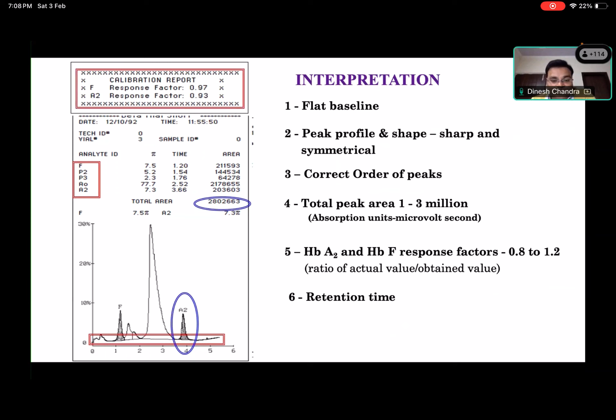Before interpreting any graph, we should always look at it very carefully for a few things. Whether the baselines are flat, then what is the retention time of your A2, then all the peaks. It should not be that A2 comes before A. That means there is something wrong. Then the total area should be between 1 million and 3 million. And the response calibration curve should not be below 0.8 or more than 1.2. So that is what we have to look for.